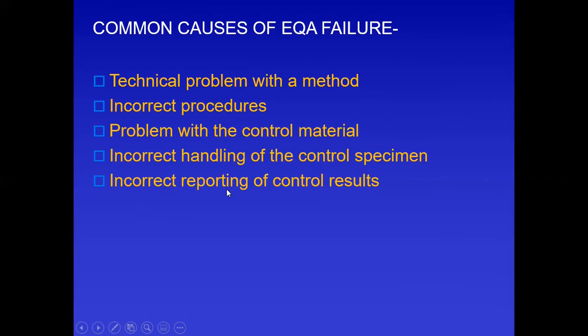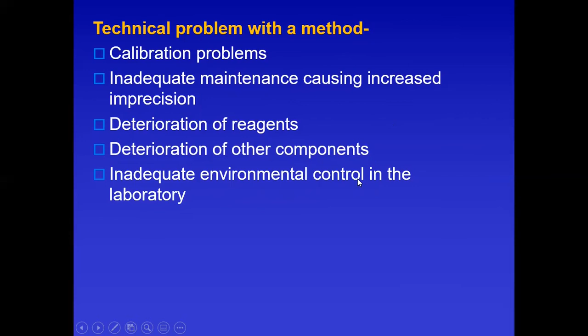Now I'll talk about how to troubleshoot EQAS failure. So what are the causes for EQAS failure? Common causes of EQAS failure are technical problem with the method, incorrect procedure, problem with the control material, incorrect handling of the control specimen, and incorrect reporting of control results. Technical problems with the method include calibration problem, inadequate maintenance causing increased imprecision, deterioration of reagents, deterioration of other components, and inadequate environmental control in the laboratory.